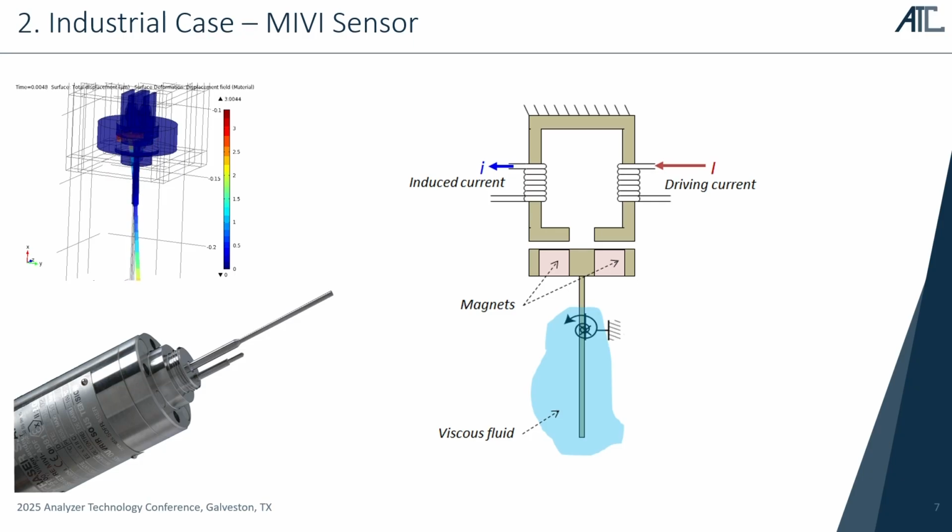In the 70s, Sofraser patented the first viscometer using vibrational technology at resonance frequency. Sofraser now has more than 50 years of experience in viscometry. We have more than 40,000 viscometer users worldwide. We are present globally. I'm going to talk about the working principle of the sensor. It is a vibrational type technology.